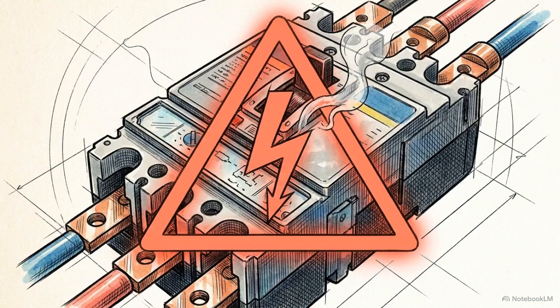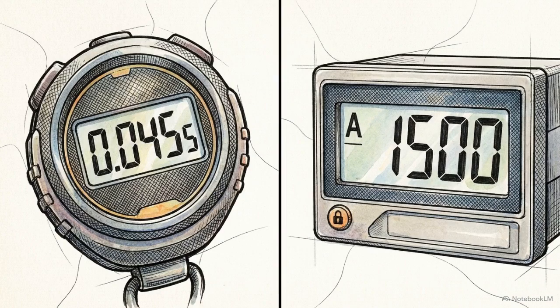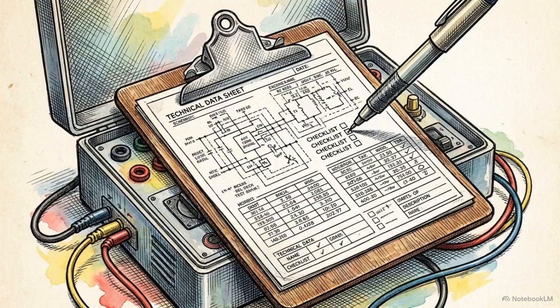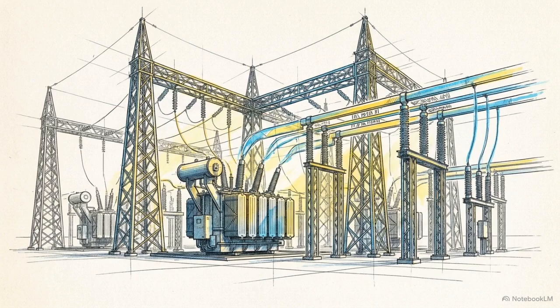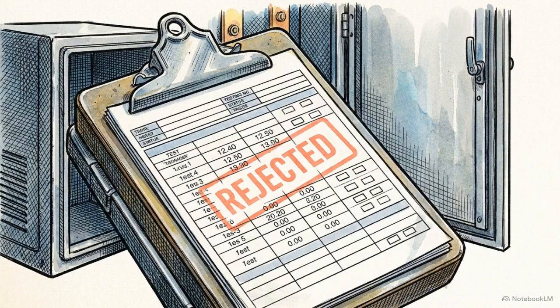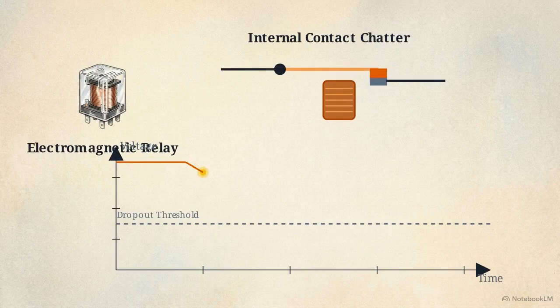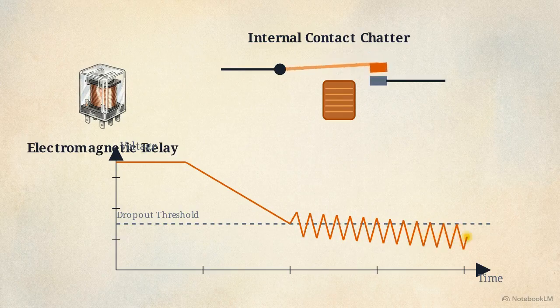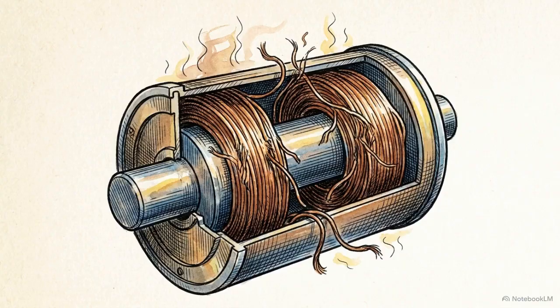Because the thermal and magnetic forces at these loads are extreme, technicians must record the time and current from the display simultaneously. At 300% load, the margin for mechanical error is minimal. Recording an accurate trip under a 300% load without any structural failure validates the MCCB's capacity to arrest a catastrophic short circuit. Subjecting hardware to extreme tolerances occasionally reveals defects. Engineers document any delayed trips, absolute failures to trip, or localized abnormal heating across the terminals. If a supervision relay exhibits contact chatter or sticks during the voltage drop test, it points directly to hidden coil degradation or mechanical misalignment within the casing.